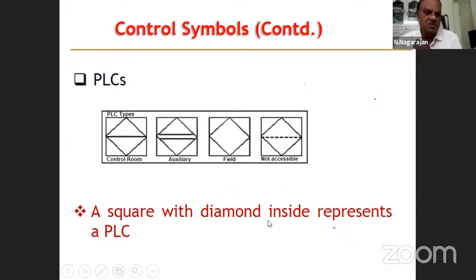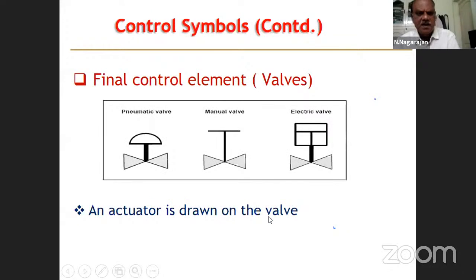PLC, we have seen programmable logic controllers. PLC types, again you will have the same. The symbol varies, means diamond inside the square. There is a diagonal line means control room, double line means auxiliary, no lines mean field, not accessible means backside of the control panel. Final control elements are valves, the pneumatic valve. If you see this kind of curved top, where the air pressure acts and which helps in opening or closing the valve, this is the pneumatic valve.